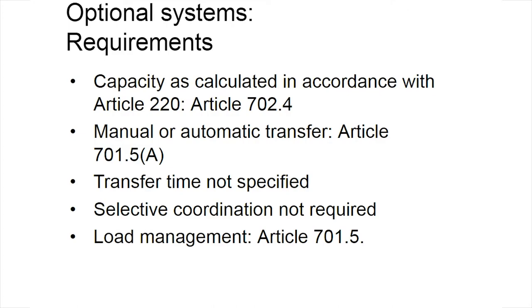The code allows for the optional system capacity to be sized under the all loads intended to be operated at once rule if the transfer is made manually rather than automatically, or if the system is protected by a load management system that restricts the total load to some level below the generator capacity. In a manual system, it also allows for a user selecting which loads will be energized.